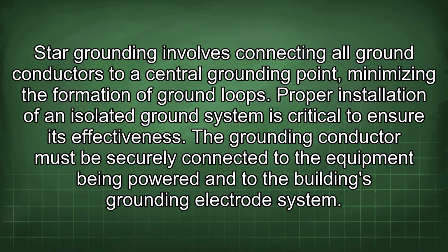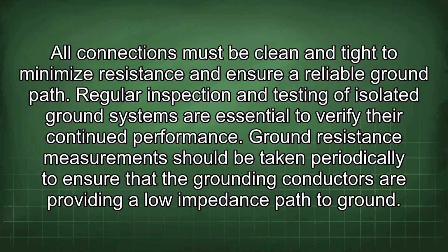Proper installation of an isolated ground system is critical to ensure its effectiveness. The grounding conductor must be securely connected to the equipment being powered and to the building's grounding electrode system. All connections must be clean and tight to minimize resistance and ensure a reliable ground path.